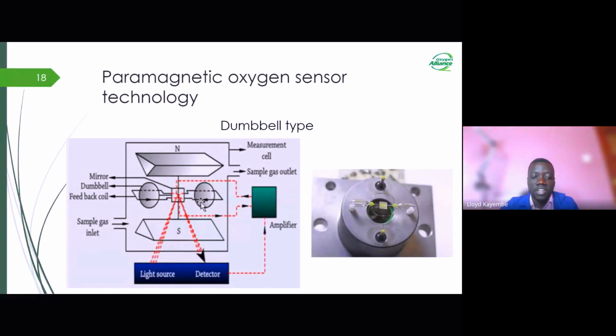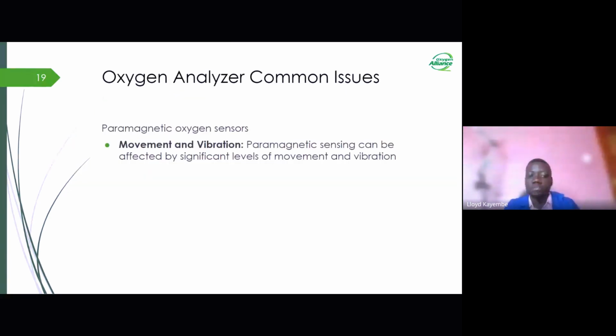So on the next slide, I'll talk about the common problems with paramagnetic sensors. Paramagnetic oxygen sensors are affected by movement and vibrations. Since the sensors have been made to sense oxygen by the movement of the dumbbells, any movement or vibration can then affect the output of the sensor. Yeah, so that's basically how the paramagnetic sensors operate.